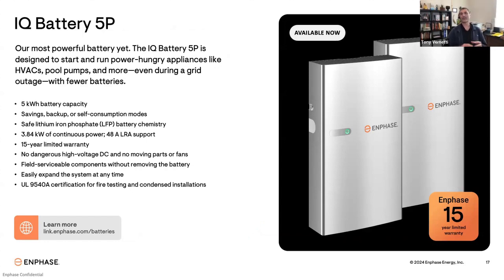So here we have sort of the crown jewel of the Enphase energy system, the IQ Battery 5P. The 5P is by far our most powerful battery yet in terms of how much power you have per unit of storage capacity per kilowatt hour. The 5P is an ideal battery when it comes to starting challenging loads off grid, like air conditioning systems or pumps. The 5 in the 5P represents a 5 kilowatt hour energy capacity. The 5P can be used either for a grid tied configuration where it's just there to save money by offsetting peak energy consumption, or, of course, for backup power systems like I mentioned.